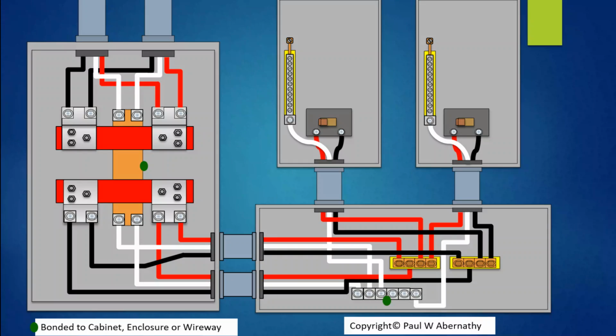Now, the reason I want to show you this graphic right here is simply to illustrate the connections. Here you've got two PVC schedule 40 or 80. We don't signify at this point. Coming into this CT cabinet, here we see this CT cabinet bonded right here to the neutral conductor, and we'll talk about the allowance for doing such a thing later. And then, of course, you see them coming over, and this enclosure is bonded to the grounded conductor at this notation here. Again, using the same principles that we did over here.